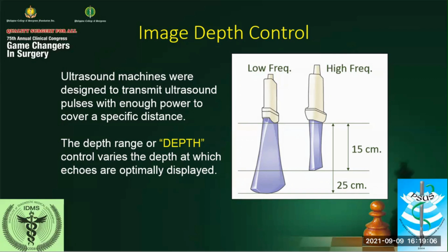Even if the machine is capable of 25 centimeters depth, if you are using a high frequency transducer such as this one, your penetration will be limited to 15 centimeters.